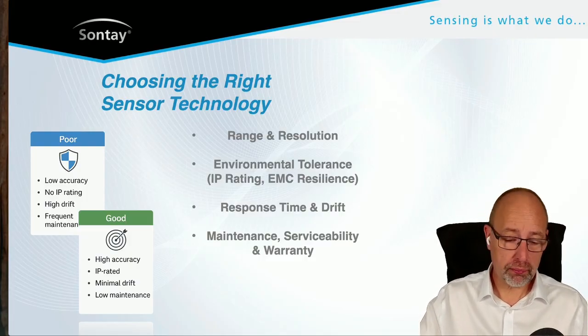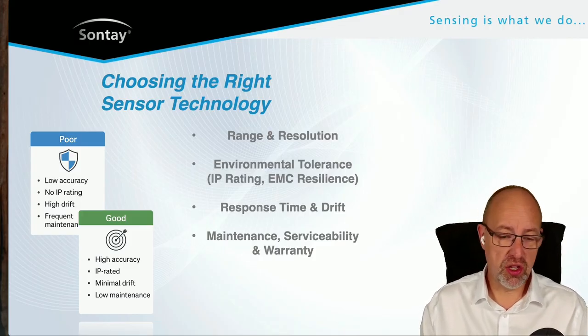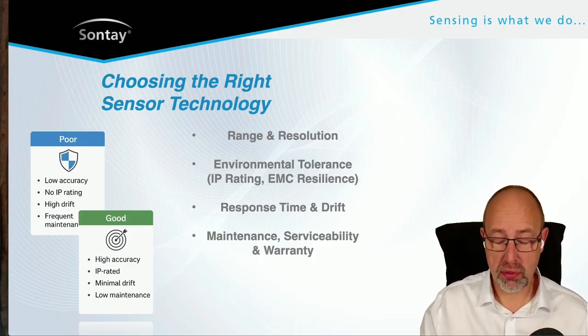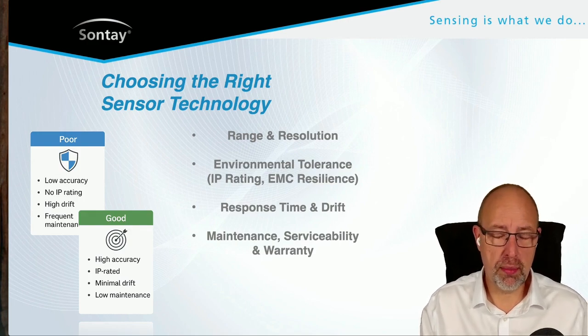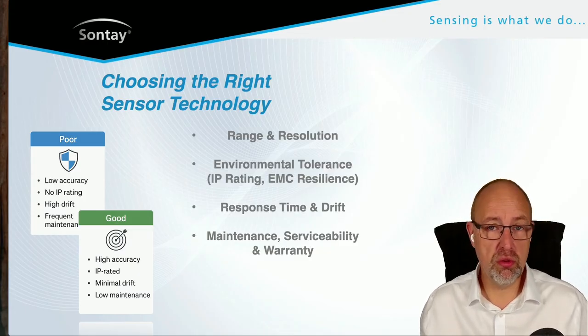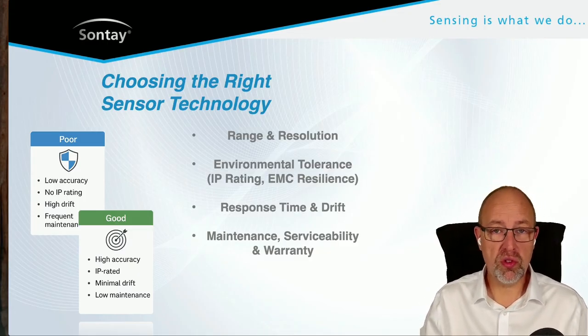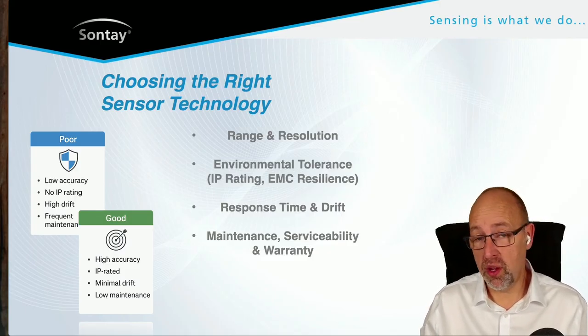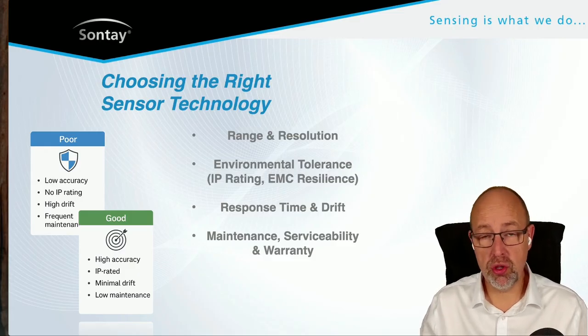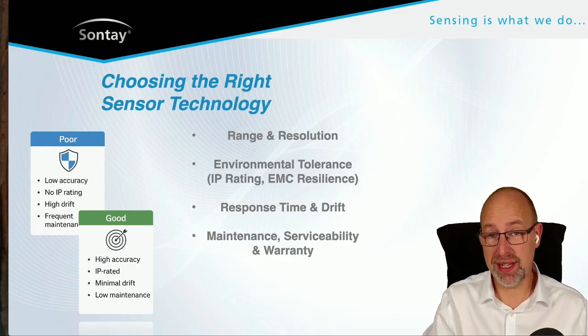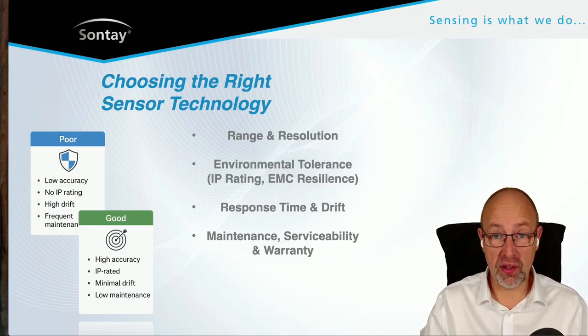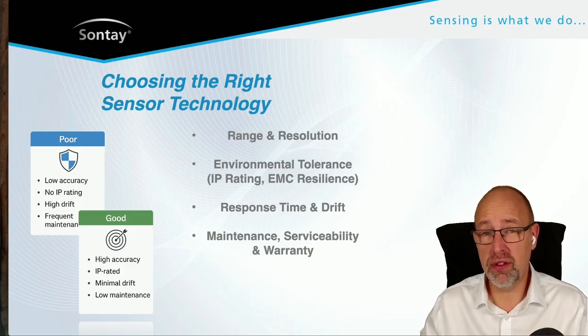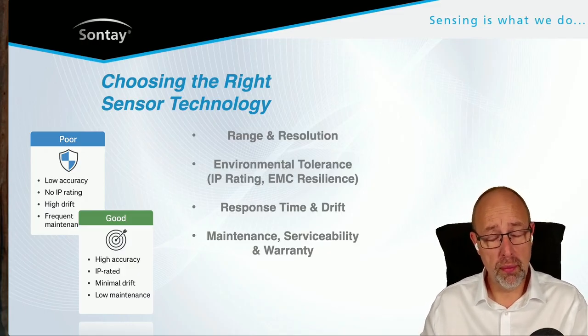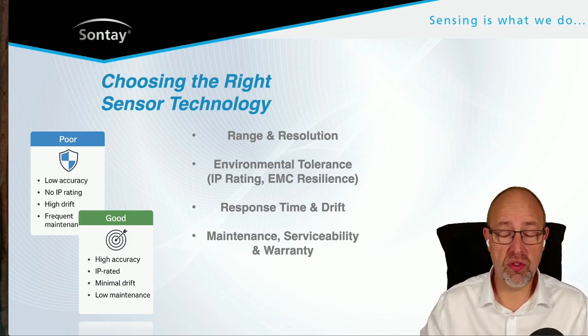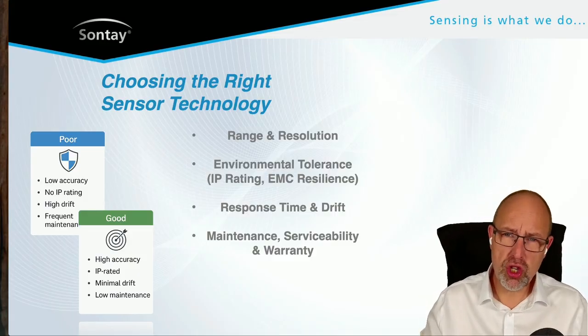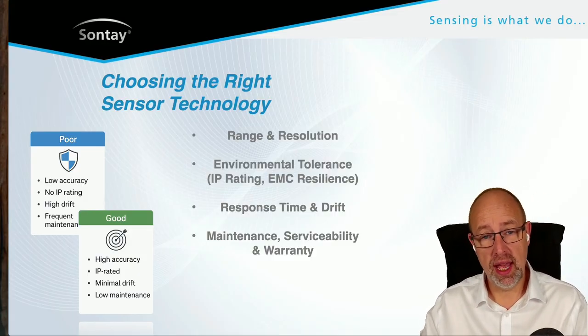A really good example of that is with pressure transducers. If we're looking at a water pressure transducer, you can get one that does 0 to 500 millibars, so 0 to half a bar. You can get ones that do 0 to 40 bar. Now, both of those will sense 250 millibars, but one of those is going to give you better accuracy because the resolution is better. If that 0 to 10 volt signal represents 0 to 40 bar, then 250 millibars is going to be a very small voltage, which is going to be very difficult to measure. Whereas if you've got the 0 to 500 millibar pressure transducer and you're looking at a working range of 250 millibar, that's 5 volts. So you get much better resolution. So choosing the right range and getting the right resolution for your sensors is really important.